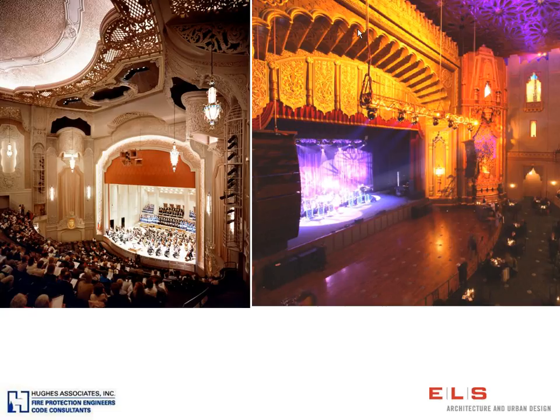But as a fire protection engineer, I like to install systems that are going to be effective. And what happens when your floor area, or your area where your potential fuel load would be on the floor, gets too far away from the ceiling, say 50 feet or higher or so, your sprinkler system cannot be effective. What happens is that, one, the sprinkler system may not operate, because as the heat rises, it is cooling. And so by the time it gets to your ceiling, it might have cooled to the point where it won't activate your 165-degree sprinklers.